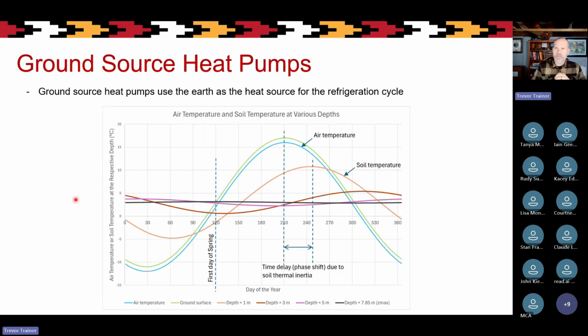So first, let's talk about ground source heat pumps. Ground source heat pumps use the earth as the heat source for that refrigeration cycle. Instead of trying to pull heat out of the air, it pulls heat out of the ground. And there are some real big benefits to that. If we look at this chart, these two lines show the ambient air temperature over the course of a year. So minus 10, minus 15 in the winter, above 15, 20 in the summer. And so the air temperature is changing quite a bit. But what these other lines show us is what's happening below the ground, depending on what depth we're going.